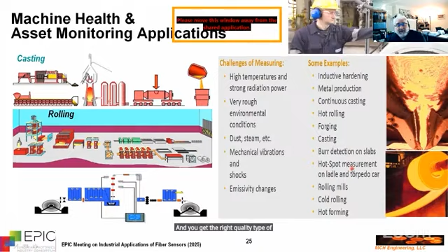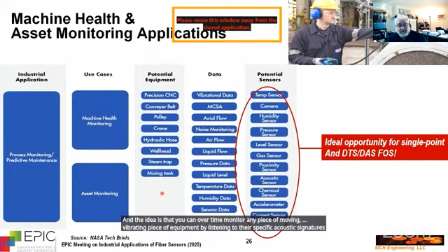One area I think is completely unexploited at the moment is condition monitoring, particularly through acoustic sensing—very typical and common in piezoelectric and other acoustic sensing devices. The idea is that you can, over time, monitor any piece of moving, rotating, or vibrating equipment by listening to its specific acoustic signatures and how they change over time.